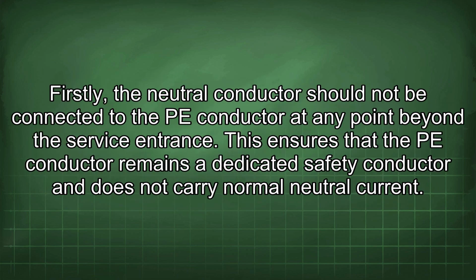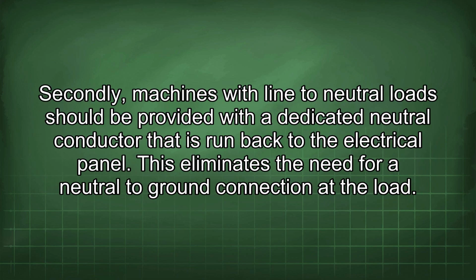implemented. Firstly, the neutral conductor should not be connected to the PE conductor at any point beyond the service entrance. This ensures that the PE conductor remains a dedicated safety conductor and does not carry normal neutral current. Secondly, machines with line to neutral load should be provided with a dedicated neutral conductor that is run back to the electrical panel. This eliminates the need for a neutral to ground connection at the load.